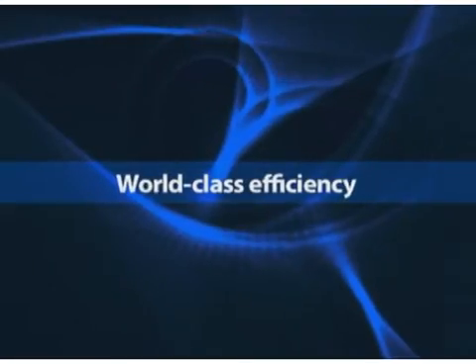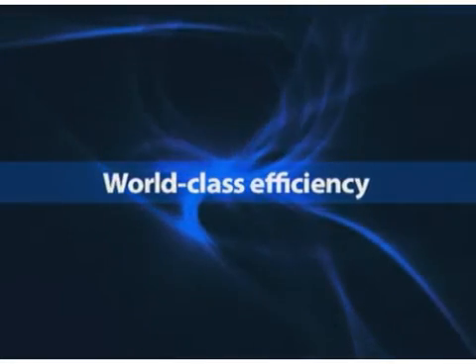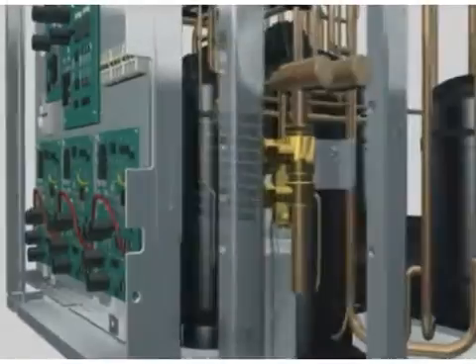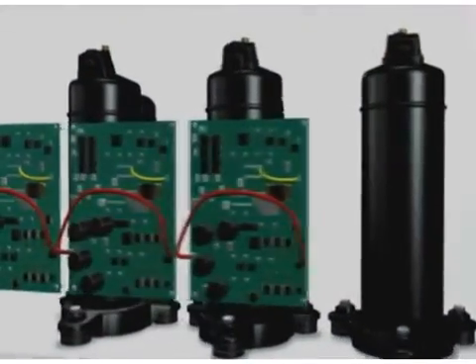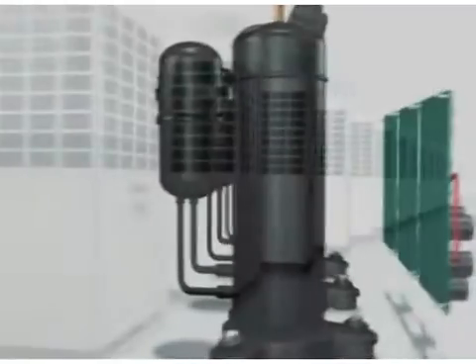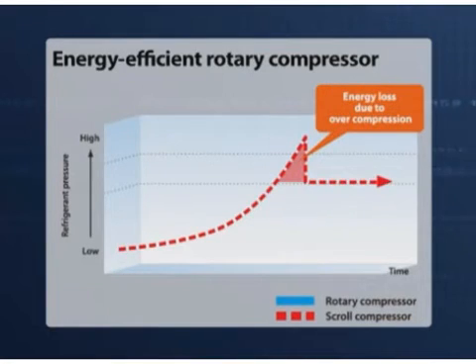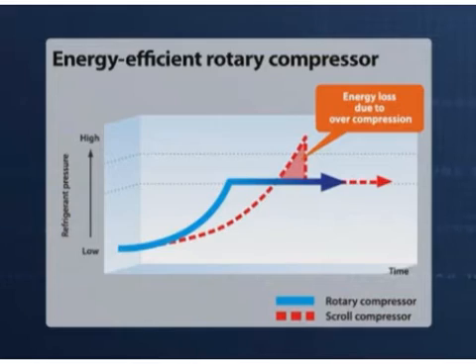SHRM-i integrates Toshiba's leading-edge technologies that effectively work together to provide world-class efficiency. Innovative and efficient DC twin rotary compressors afford outstanding performance under partial load, delivering both high energy efficiency and comfort levels. Unlike scroll compressors that initially need to exceed capacity in order to achieve a target partial load, rotary compressors can efficiently reach the same target load without energy loss.